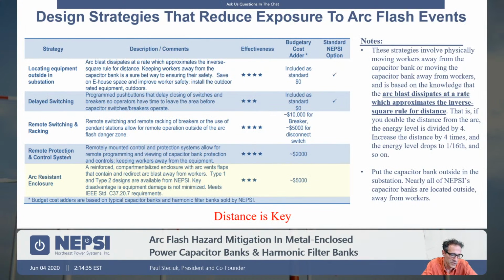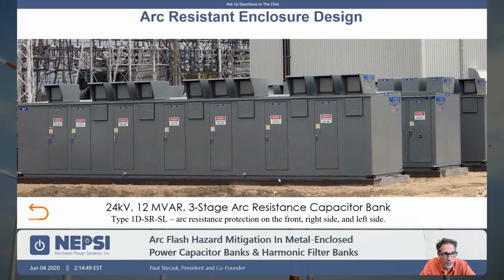Remote control and protection systems are something to think about. If the control and protection system is remote, then all the switching operations are in fact done at a remote location. They're not standing next to the medium voltage equipment. Arc resistant enclosure: this is something to think about, and NEPSI has developed arc resistant enclosures. The concept of an arc resistant enclosure is that if we have a fault inside the enclosure, we expel the gas out the rear or out the top. We vent it away from where people may be standing.